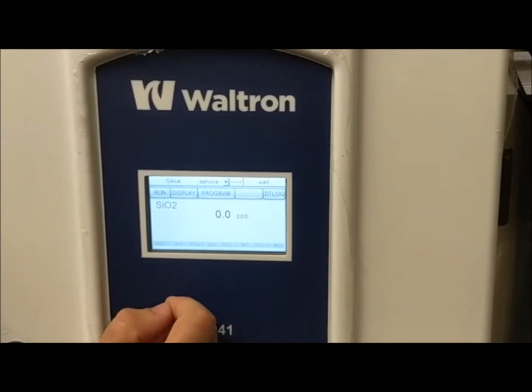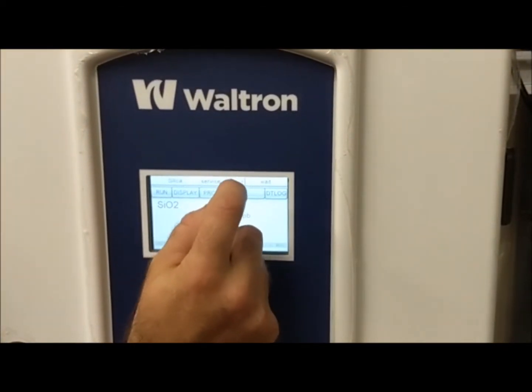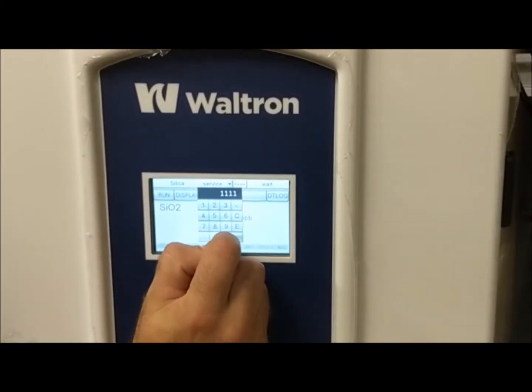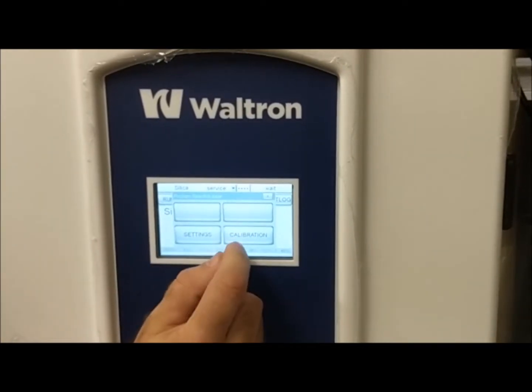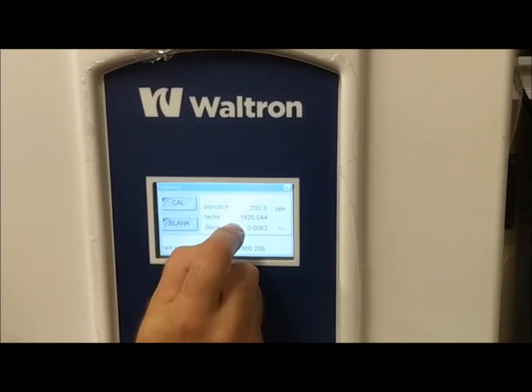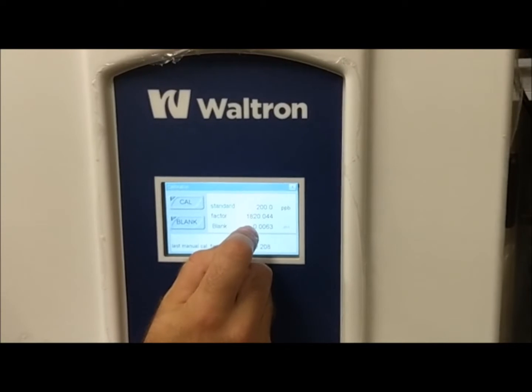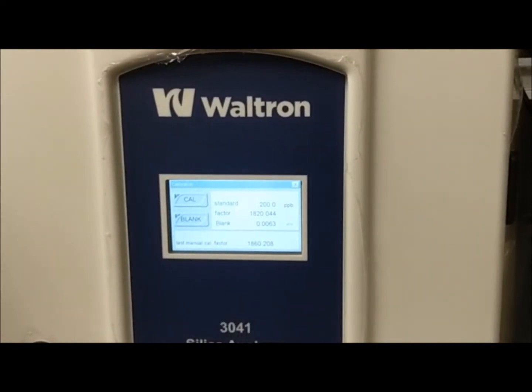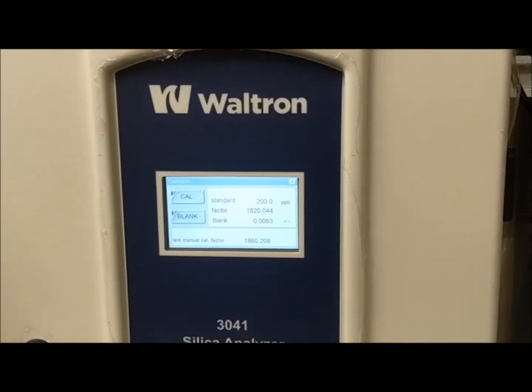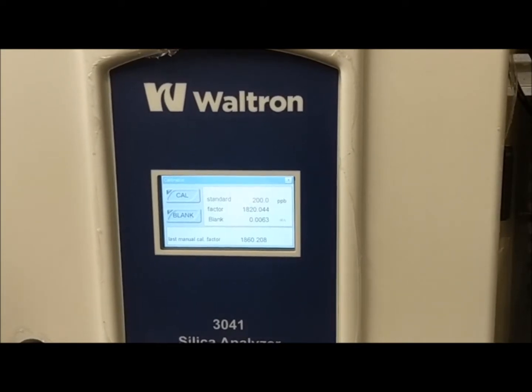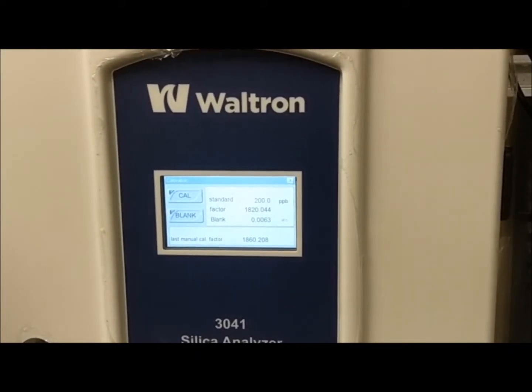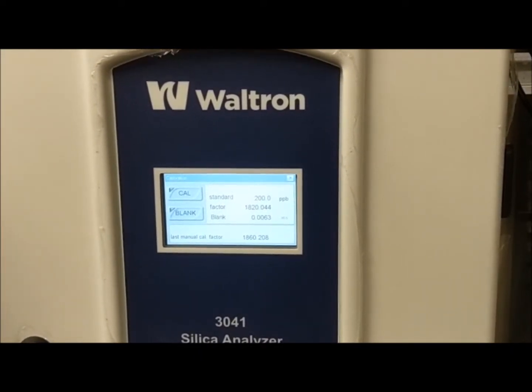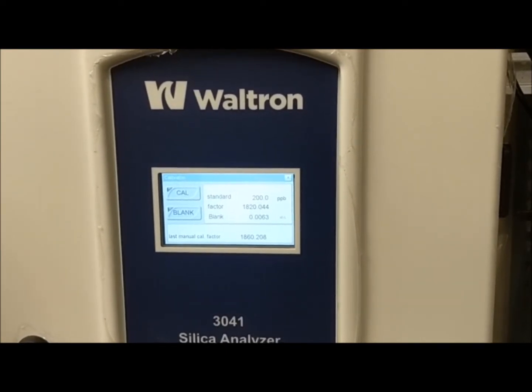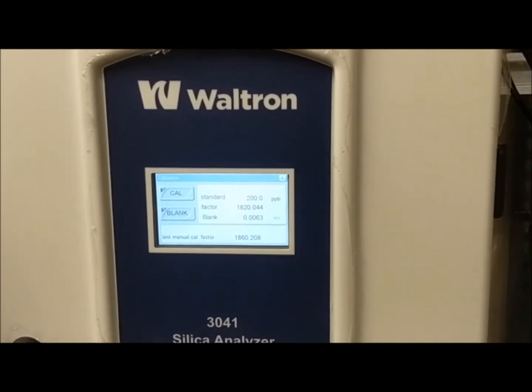To check our calibration factor, we would log in with the service password, 4 ones, come to Program, Calibration, and this calibration factor right here is the latest calibration factor that the analyzer has calculated. Outside of a range of approximately 1400 to 2500 you get a cal failure alarm. As long as the factor is within that range, the analyzer considers it a good calibration, updates the factor, and is ready to go online.